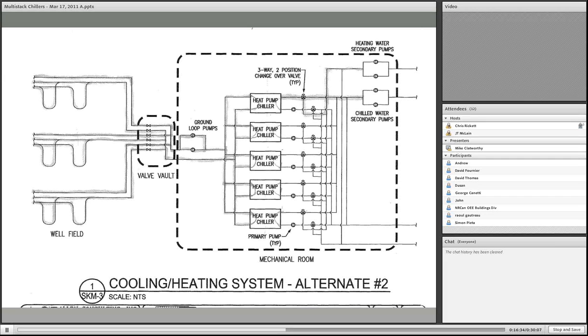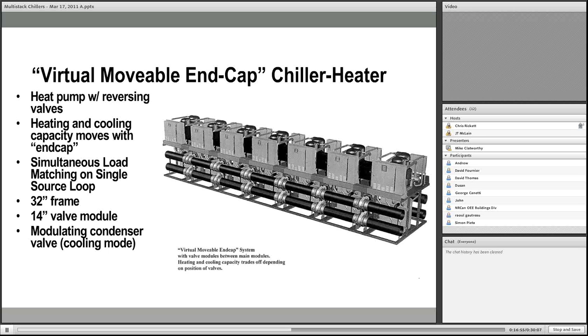So in the slide here, what we've got there is really a typical distributed water source heat pump system on a building, where you've got water-to-water heat pumps located all around the building. So you've got compressors located everywhere. You've got potential maintenance problems located all around the building. And so what we're really going to do is offer something that not only is energy efficient and provides a lower carbon footprint, but basically eliminates having multiple water-to-water heat pumps all around the building.